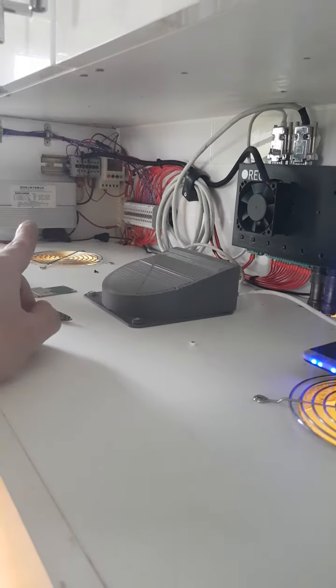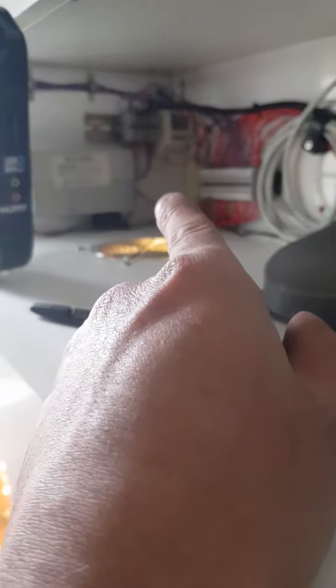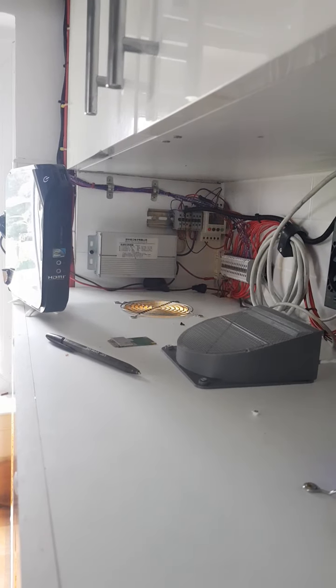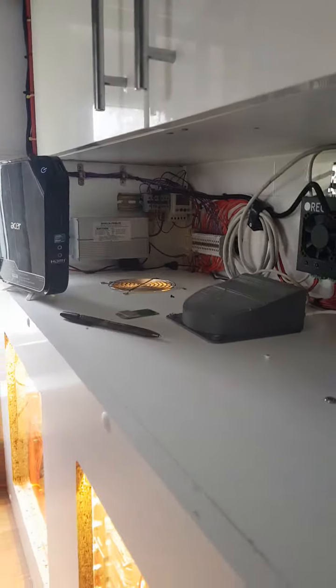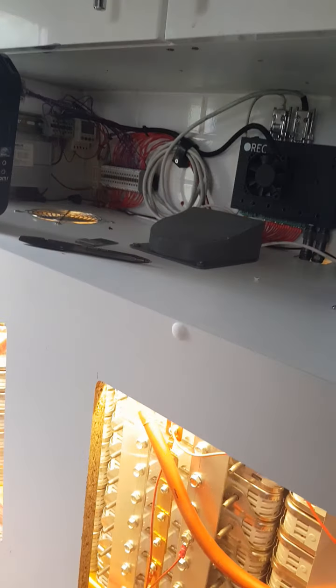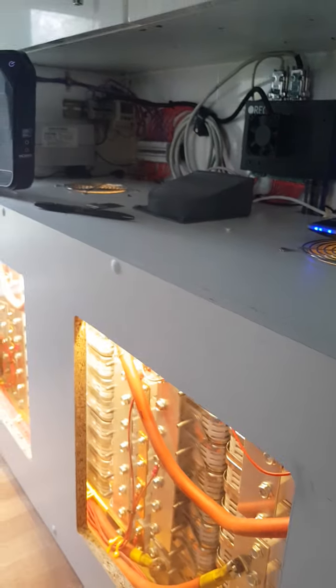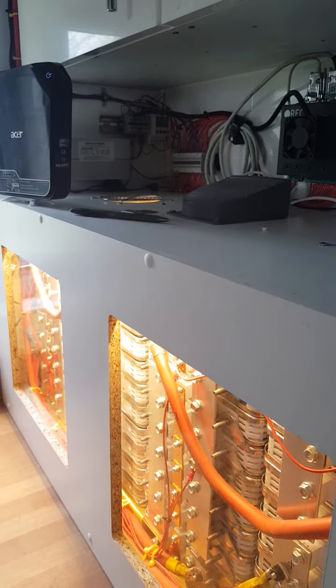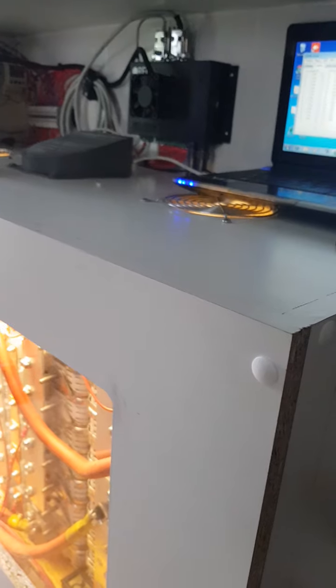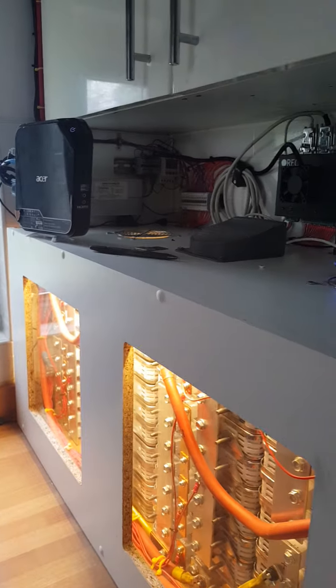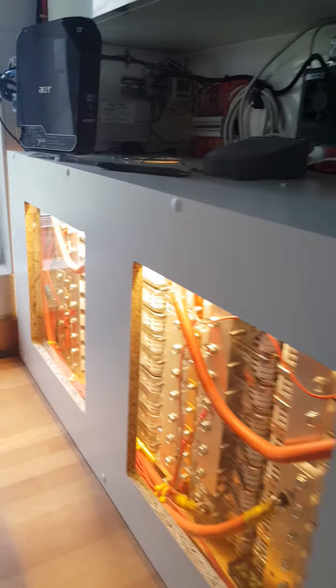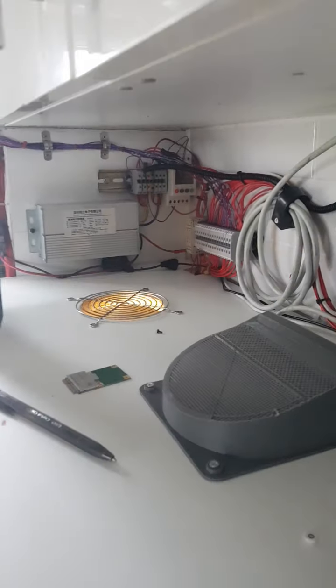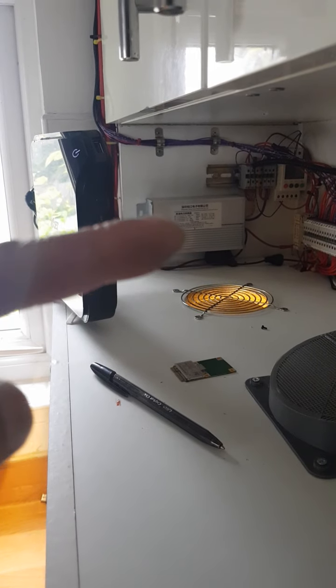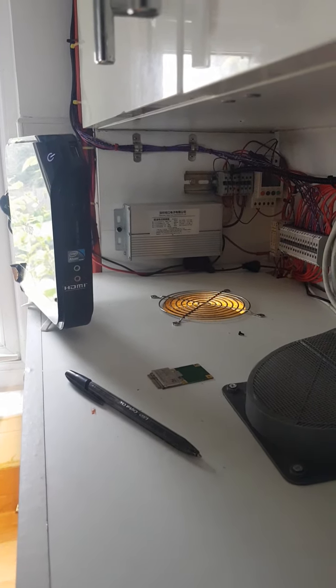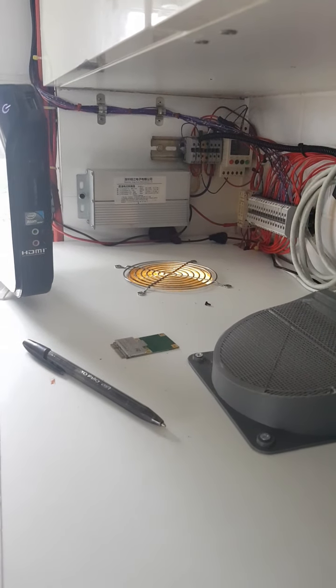Make sure when you get that, this one I think is good for about 300 watts, if I remember rightly, so just make sure you buy one that can do the wattage and go over the top. I mean, yes, we've got a couple of fans and one contactor here - that's not going to take anywhere near 300 watts, but you want this to be in service for however long. So this way for definite you've not overloaded it. Don't get one that's just 60 or 70 watts and then find out it burns out after a year and a half.